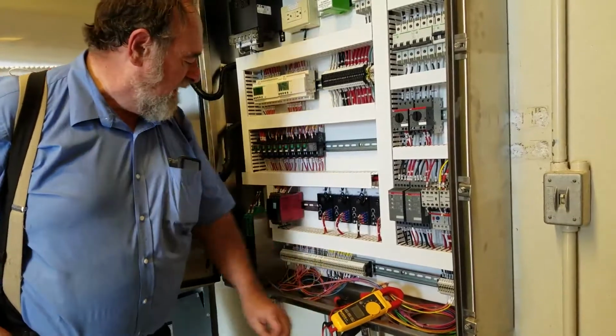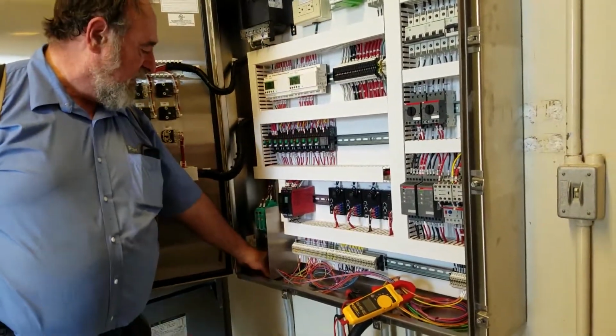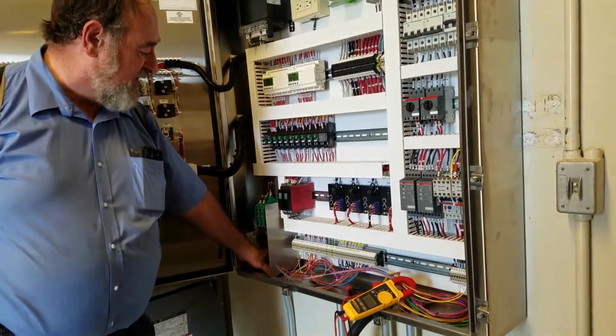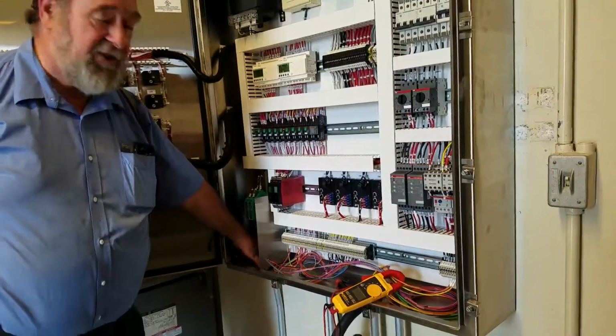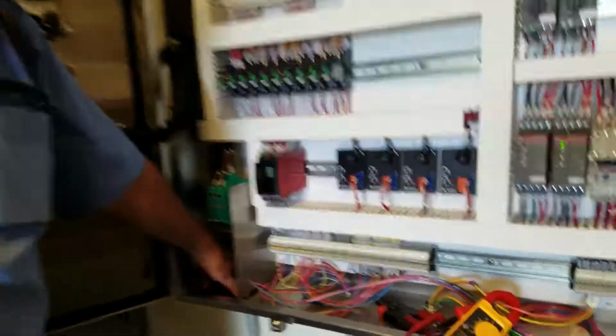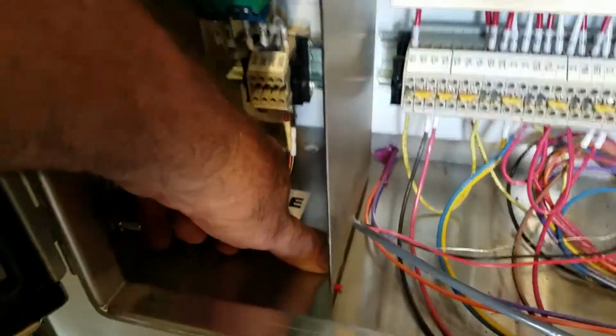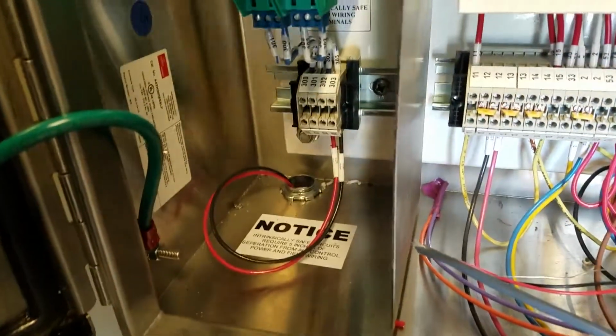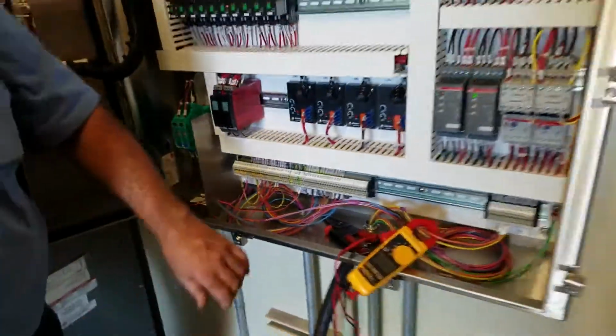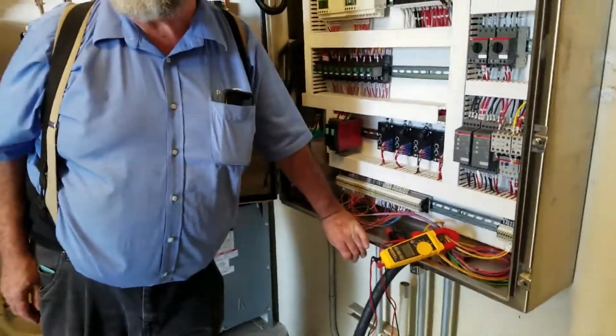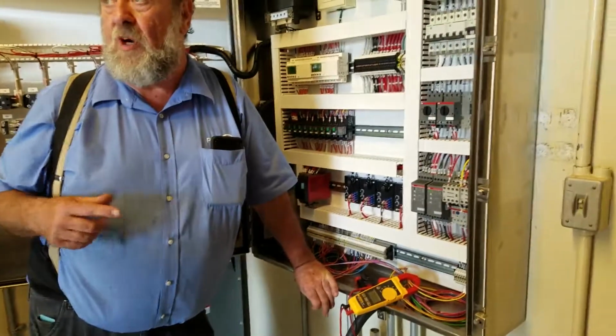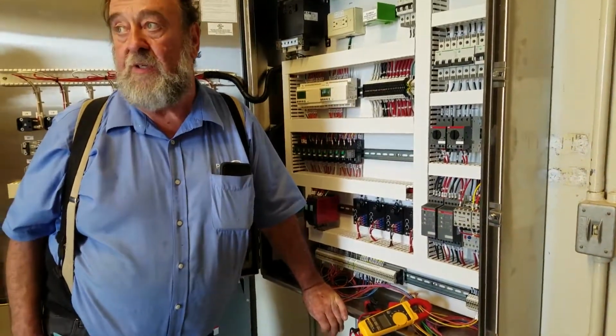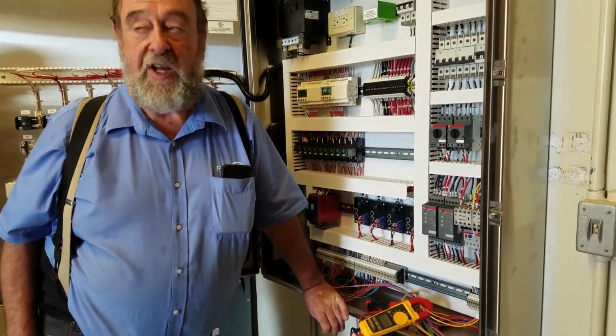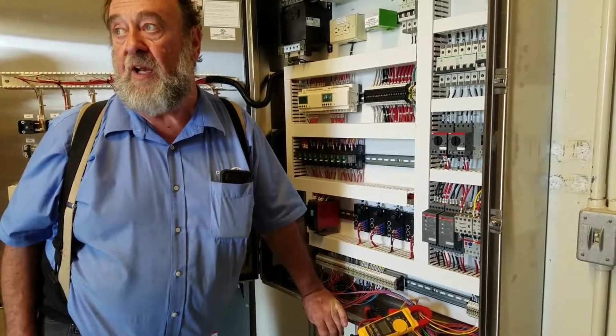Now, when they get all done hooking up these process sensor wires, it'd be a good idea to seal this conduit with some duct seal or silicone, to keep the bad air from coming back through. Right, and the other thing I told John is use some of those gel type wire nuts or connectors to make sure you don't get corrosion on that, because it's low voltage. If it's not 120 volts, you're going to end up having a problem eventually. You don't want that headache.